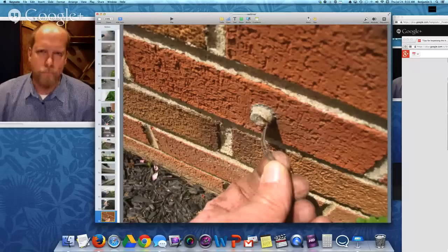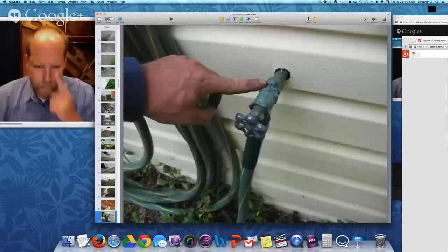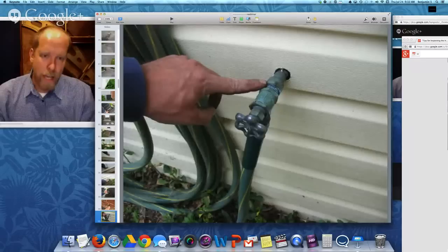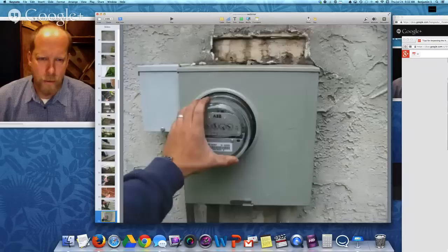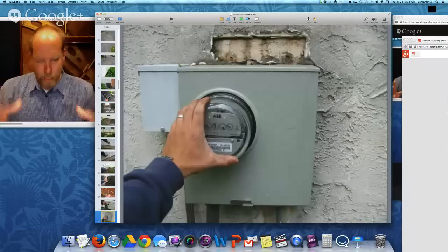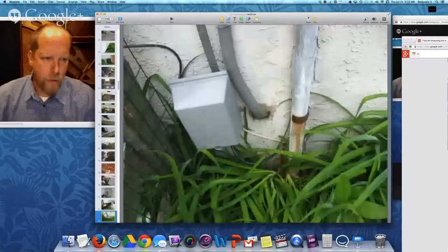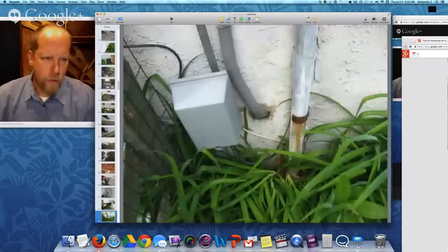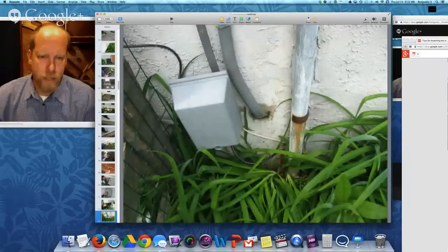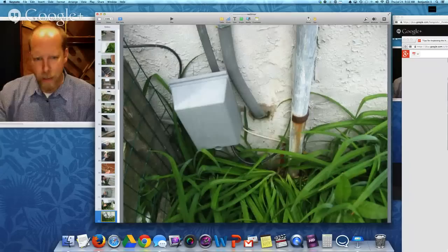There's some kind of component attached to the wall — old antenna, possibly. Water pipes that come through the building envelope can be a pathway for insects, vermin, and water. That's not a frost-free hose bib, so it could freeze and burst in wintertime in northern climates. The electric meter — I like to grab it gently and give it a little tug; it should be securely fastened to the wall. This one was replaced from a 100-amp to 200-amp service, which is great. The grounding wire also penetrates the wall envelope and could be a pathway for water penetration. The electric conduits going into the service line are also sometimes a pathway — I've found they can bring water into the electrical panel in the basement.